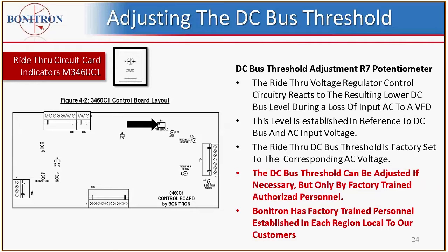Now, one of the most critical components on the ride-through control board is the DC bus threshold adjustment R7 potentiometer. The ride-through voltage regulator control circuitry reacts to the resulting lower DC bus level during a loss of input AC to a VFD. So in other words, this adjustment is very critical as far as telling the ride-through when to turn on in relation to the DC bus.